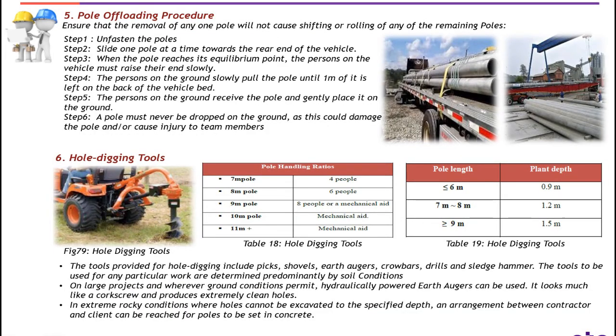Pole off-loading procedure. Ensure that the removal of any one pole will not cause shifting or rolling of the remaining poles. Step 1: unfasten the poles. Step 2: slide one pole at a time towards the rear end of the vehicle. When the pole reaches its equilibrium point, the person on the vehicle must raise their end slowly. The person on the ground slowly pulls the pole until one meter of it is left on the vehicle bed. The person on the ground then receives the pole and gently places it on the ground. A pole must never be dropped on the ground as this could damage the pole or cause injury to team members.